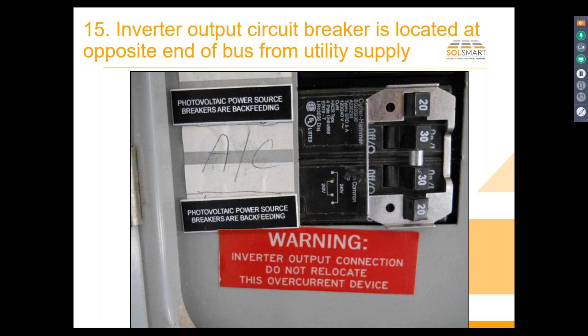Inverter output circuit is located at the opposite end of the bus from the utility supply. So basically, there's a little warning sign that says do not relocate that device. These are the labels for the DC power source. Almost all, if not all, of our DC switches are going to have a warning: electric shock hazard. Terminals on both line and load may be energized in the open position.